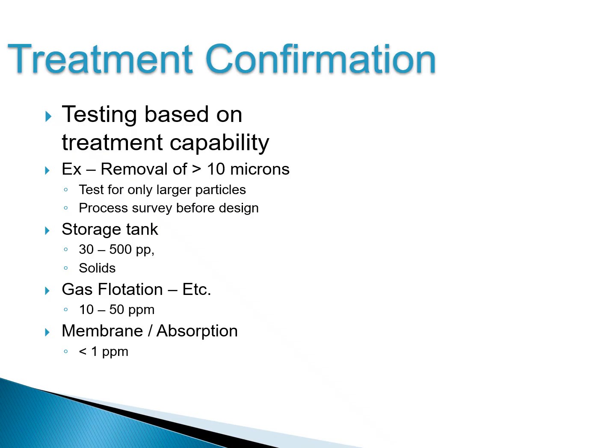So often, a water treatment system will have a rated separation efficiency or rated removal down to some concentration, depending on the size and nature of the oil droplets. So it's not just an oil concentration limit, but it is also a nature of the oil droplet limit.